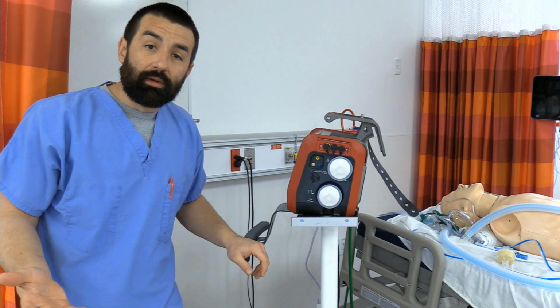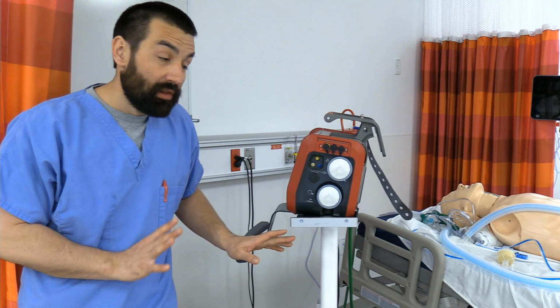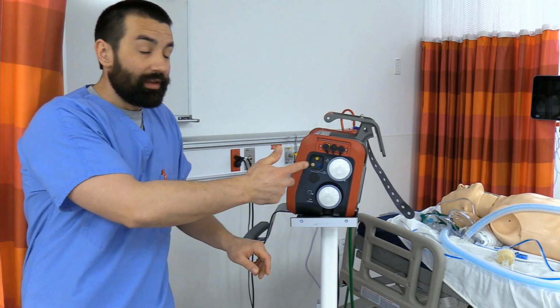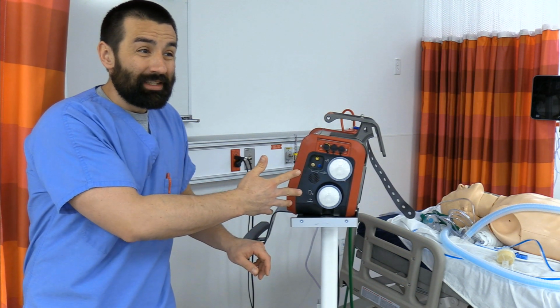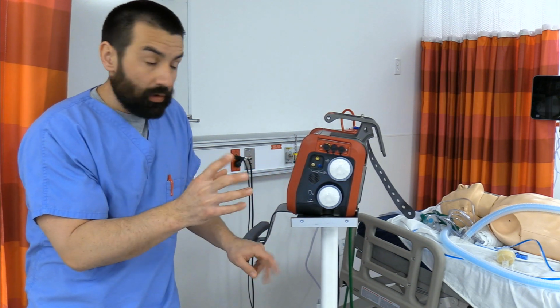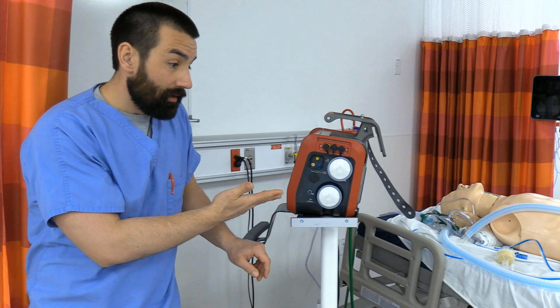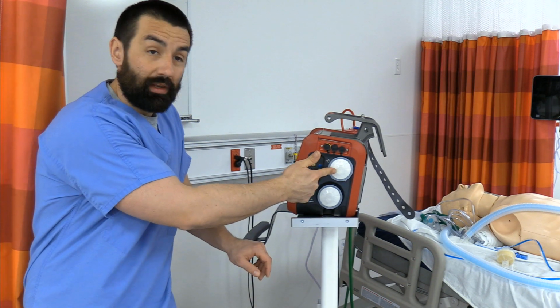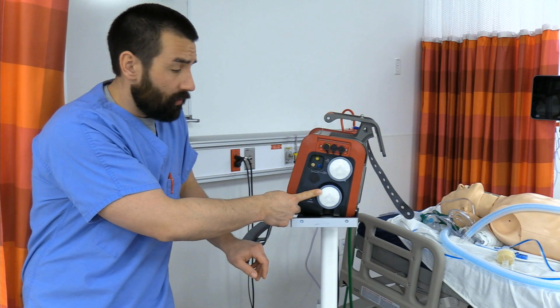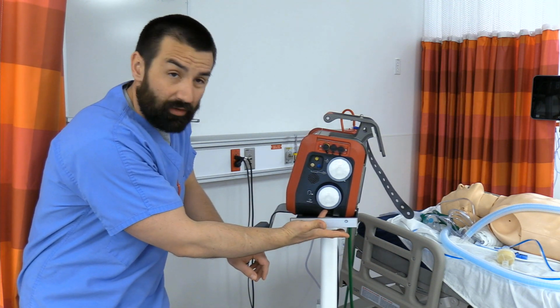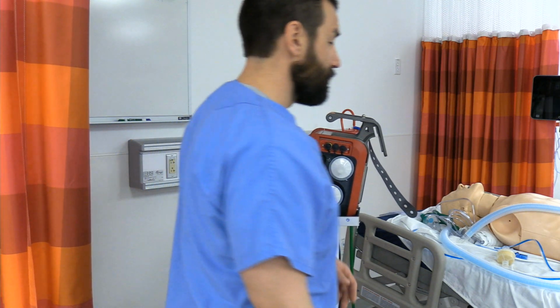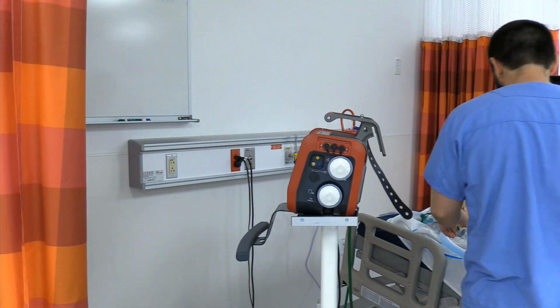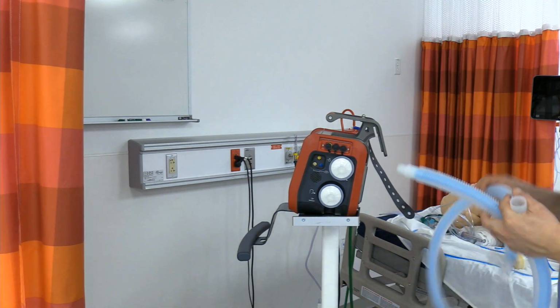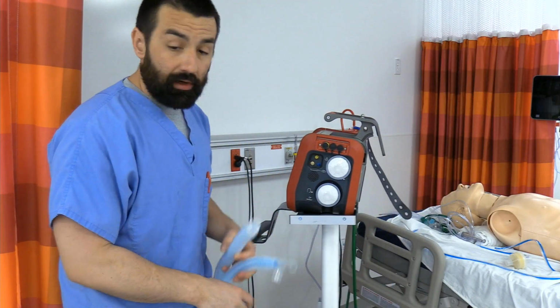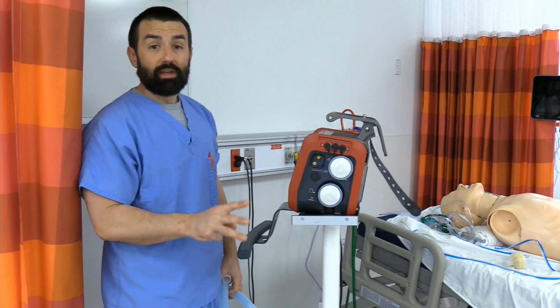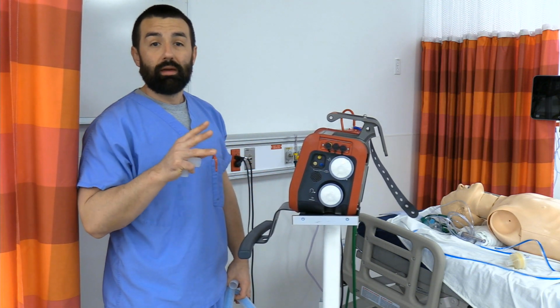With the particular circuit I'm going to show you for transport, it looks like a single limb, but in reality it's a dual limb. You really need to have a filter on both to be able to make these connections. If you're running a standard dual limb circuit, technically you get by without it. I just always filter to make sure the gas going to the patient is filtered, and then of course the expiratory side, because all that exhaled gas is coming right out down here through the exhaust. Always, always, always have a filter on there. You might even have a more heavy-duty filter type situation. So what's next? We could hook up a standard dual limb circuit, and once again, Hamilton vents are dual limb ventilators.